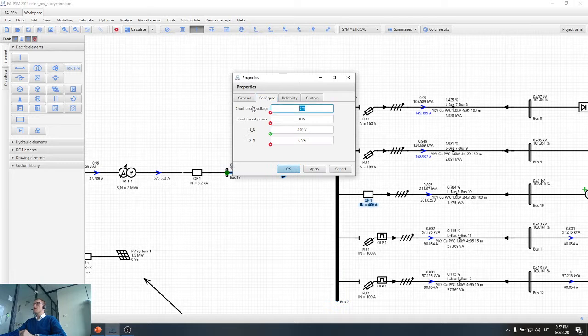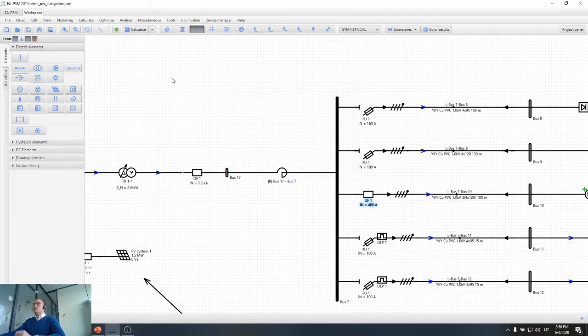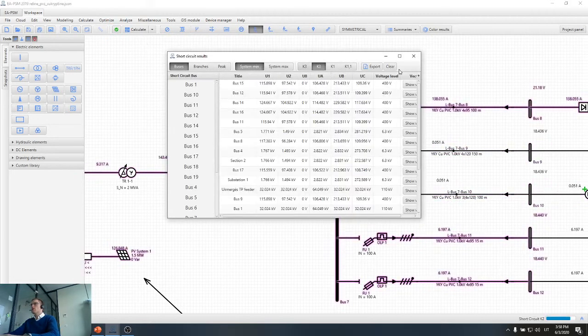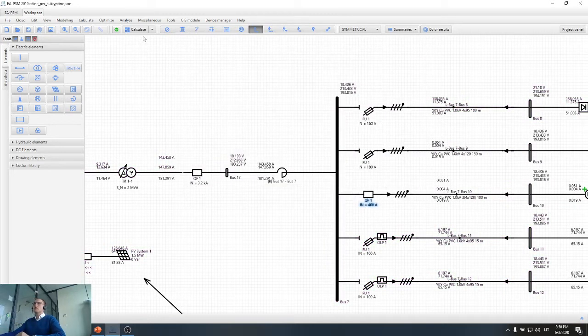So let's see what the parameters can be. For the reactor, let's take 4% short circuit voltage. Nominal power should be equal to our transformer power, let's say 2 megawatts, and short circuit power I will, let's say, provide 5 kilowatts. Okay, so we have the series reactor connected, and when we now calculate all the parameters regarding short circuits, let's go through the arc flash calculation as well with the series reactor connected.